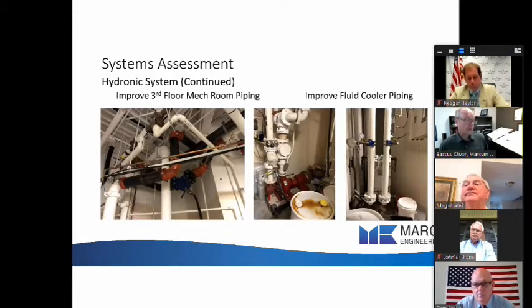I'm actually continuing on with hydronic systems. There has been a piping modification in the third floor mechanical room. You can see it in the picture on the left. It's all the unpainted pipe. I understand this was done a year or two after occupancy of the building. It was done quickly, I'll say, and not done too well. I would recommend straightening this up and making it more correct. And then the fluid cooler piping was also modified after we moved into the building. It requires the pump that you see there in the middle, and it requires the heat exchanger you see on the far right. Both of those things are just energy users that I could work around and remove and not have to have them.